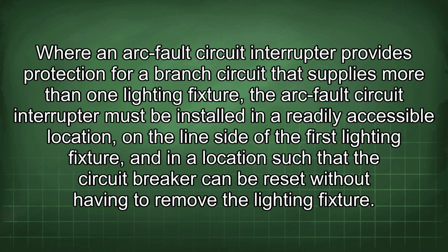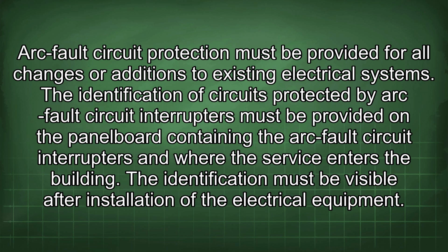Where an arc fault circuit interrupter provides protection for a branch circuit that supplies more than one lighting fixture, the arc fault circuit interrupter must be installed in a readily accessible location on the line side of the first lighting fixture and in a location such that the circuit breaker can be reset without having to remove the lighting fixture. Arc fault circuit protection must be provided for all changes or additions to existing electrical systems.